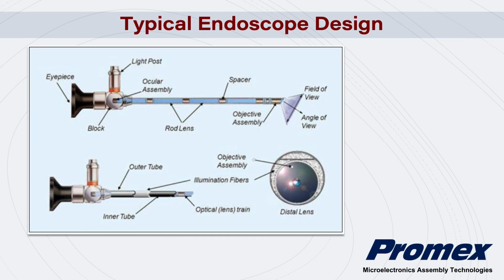In a traditional endoscope design, there is an optical chain that uses what's called an image conduit composed of a series of optical fibers and spacers. So, a few million fibers that are all in parallel to carry the image from the lens to a camera or an optical eyepiece that the surgeon looks through to see what's going on. So, you have a relatively large device with both a good deal of complexity and issues with image quality where the surgeon is essentially working through the eyepiece of a microscope.